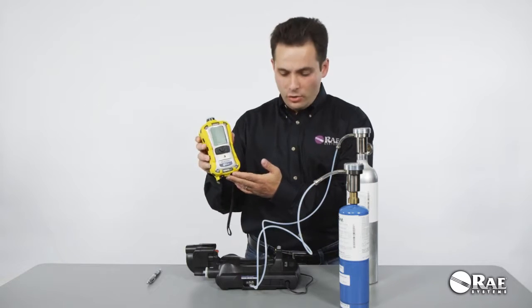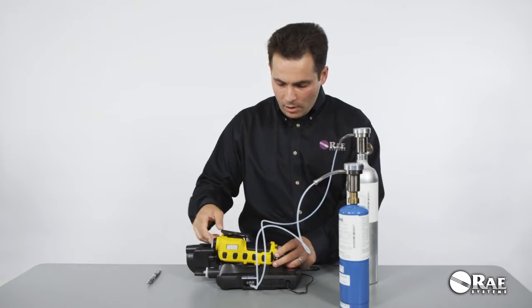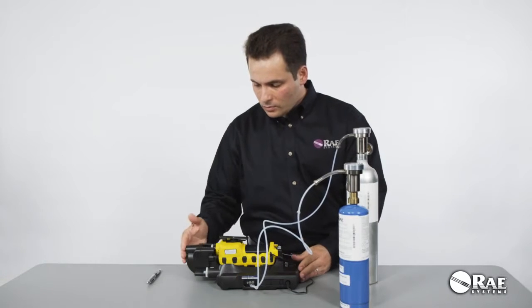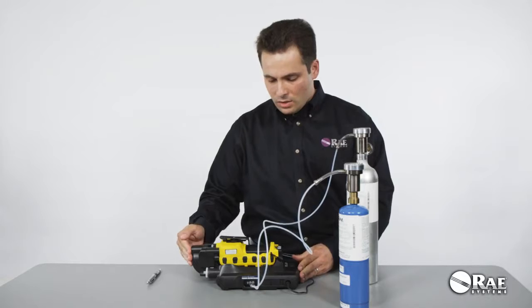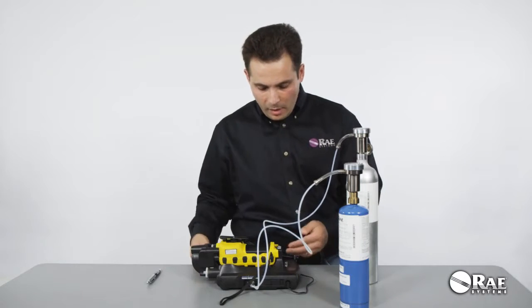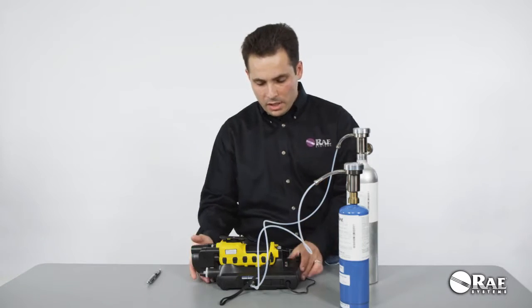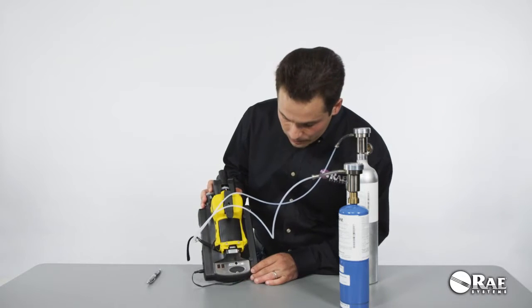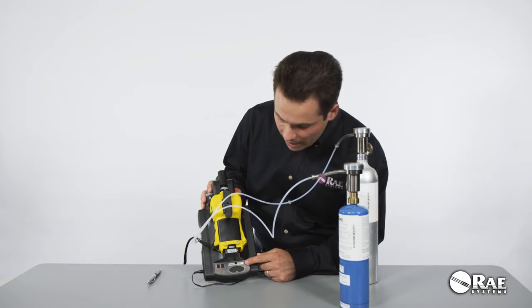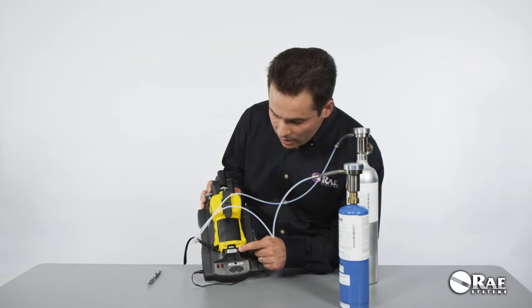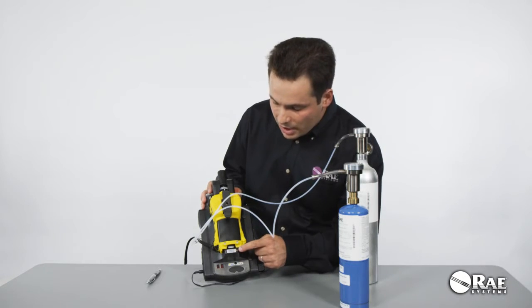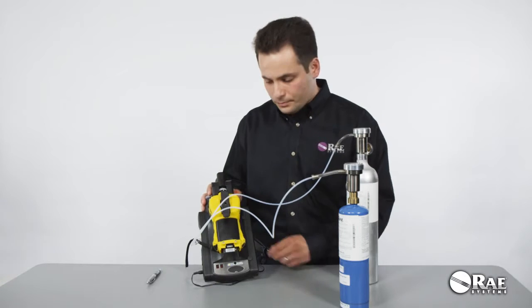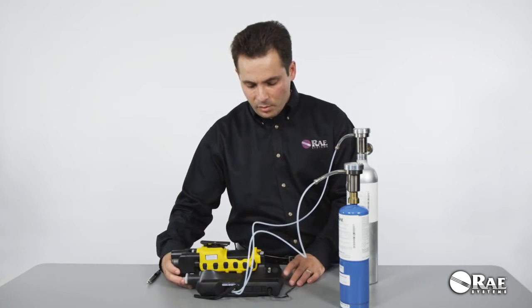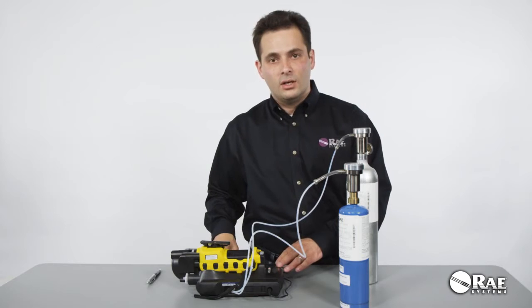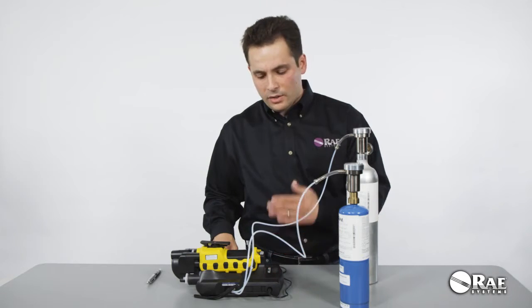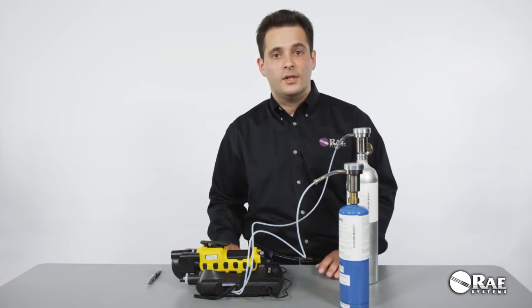So this MultiRAE is turned off, so I just put it in the cradle and lock the instrument in place, and the system will pick it up automatically and start the warm-up process like it is doing right now. So the lights are flashing, and then the charging light is also lit up to show that charging is actually in process. Once the warm-up process completes, both the LED lights for bump and cal are going to go green, and the system is ready for use. Thank you for watching.